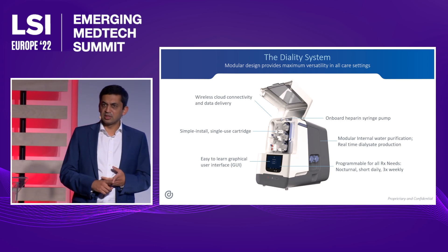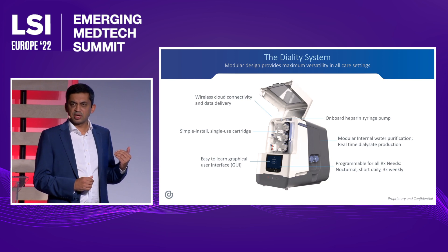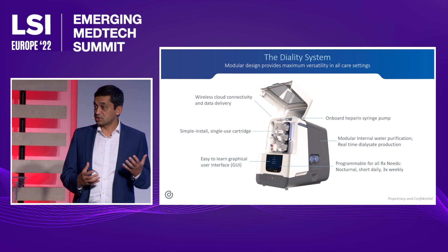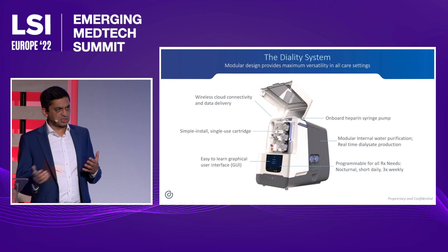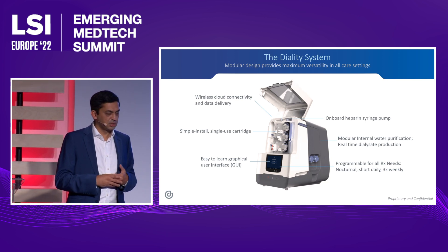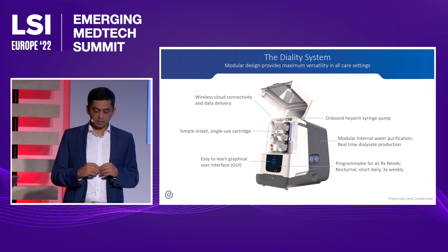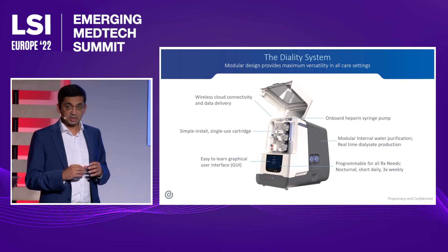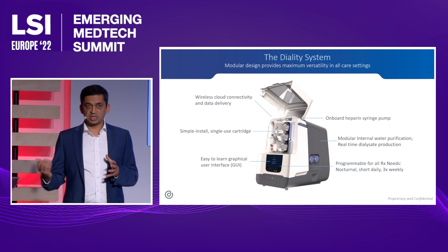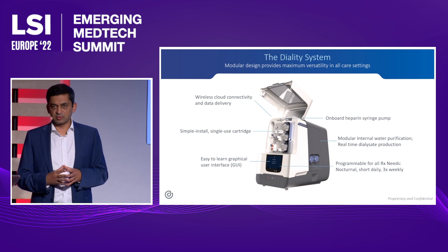There is water coming in at the back of the machine — tap water goes in. The gray area you see is the water system, like that water room I talked about. We take tap water in, filter it, purify it, heat it up, and produce pure water. We then add concentrates to make a very specific chemical fluid called dialysate. We do this in real time — water is coming in continuously and outputting at about 600 cc per minute to achieve peak performance.